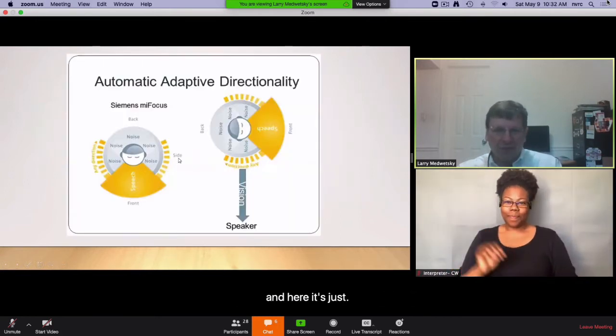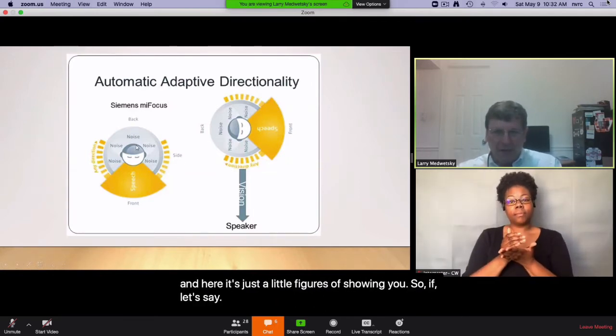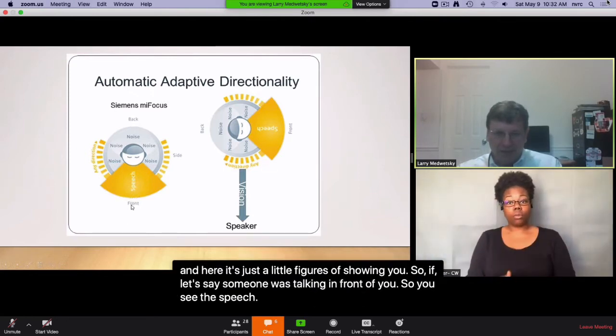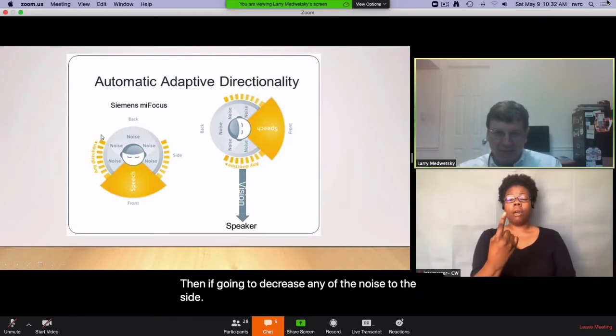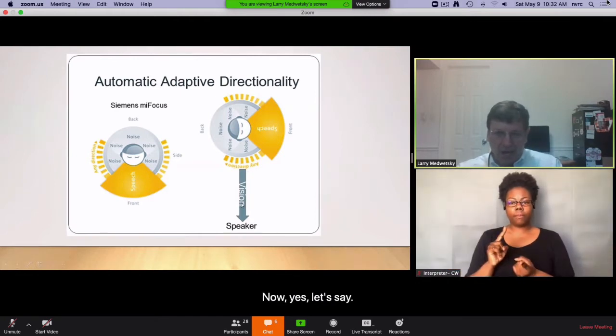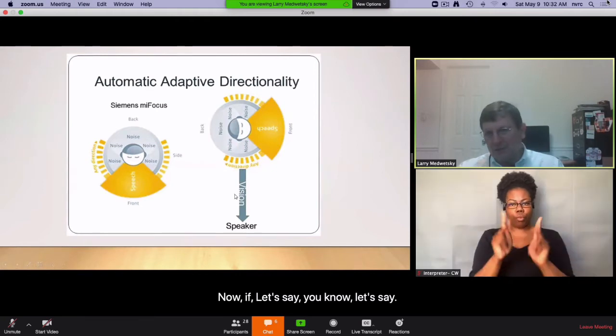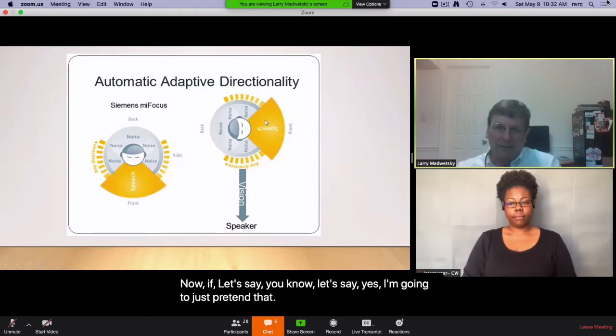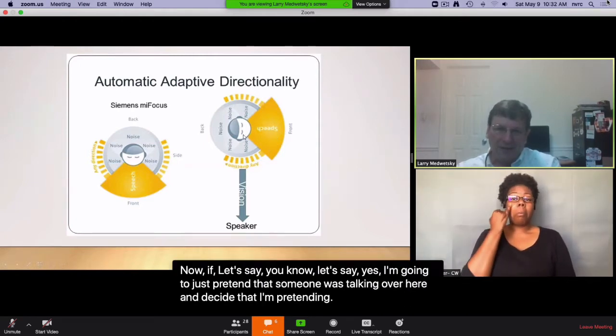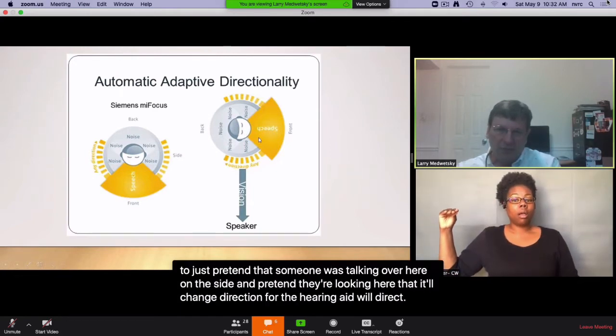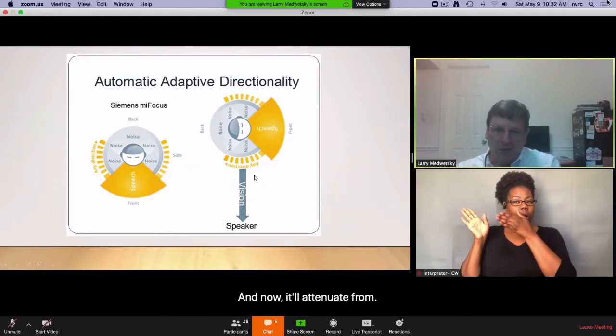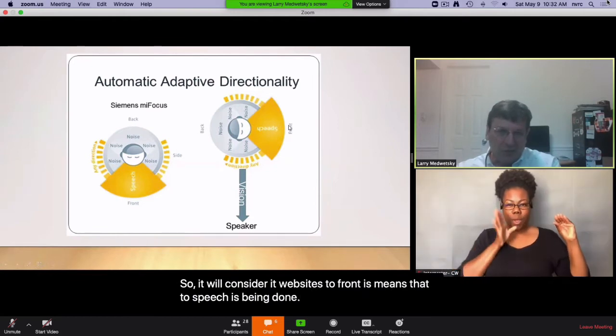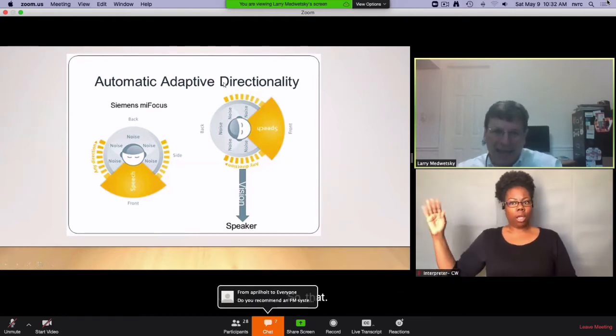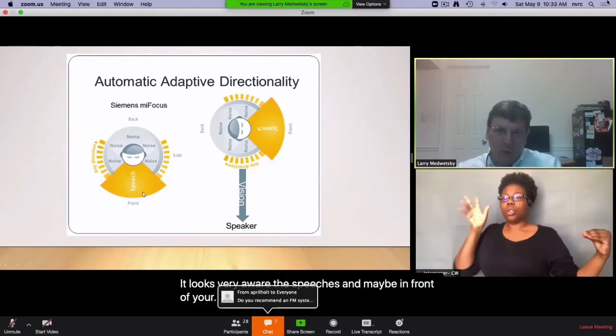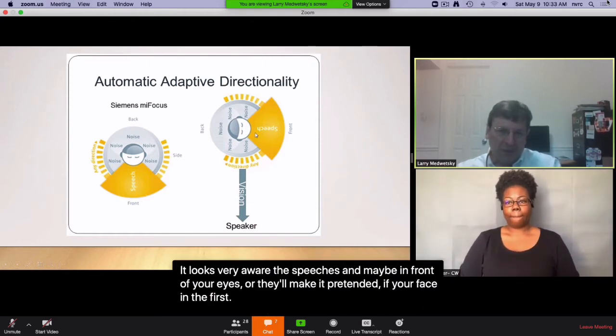And here it's just a little figure showing you. So if, let's say, someone was talking in front of you, so you see the speech here, then it's going to decrease any of the noise to the side. Now, pretend that someone was talking over here on the side and pretend they're looking here, it'll change direction. So the hearing aid will direct to the speech, and now it'll attenuate from even in front or behind. What it says here, front, means that the speech is being directed to the talker, even though that person might be to the side. So that's the adaptive. It looks for where the speech is. It'll make it pretend as if you're facing the person, even though that person's actually to your side.